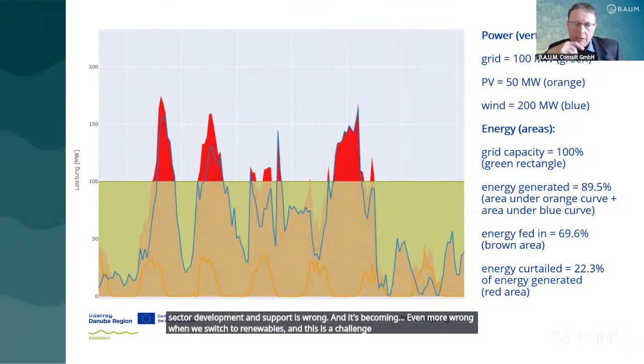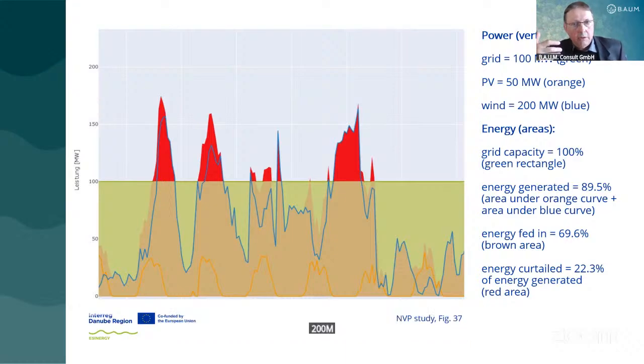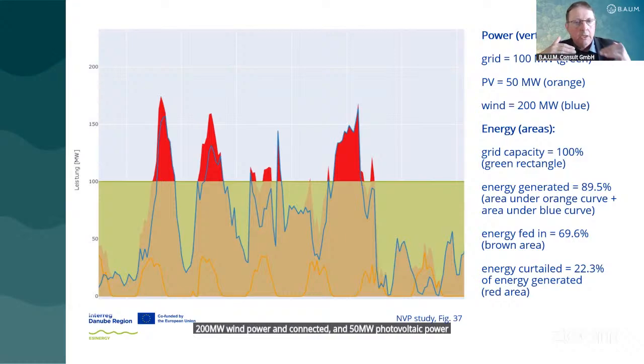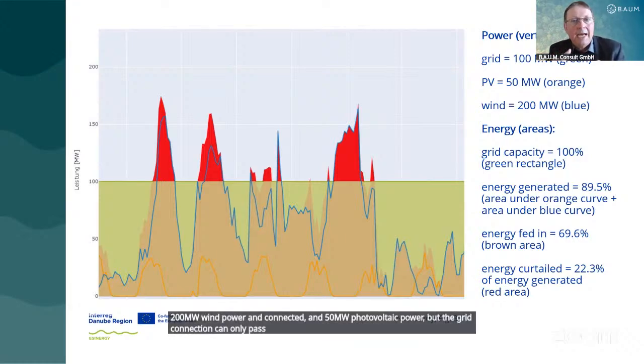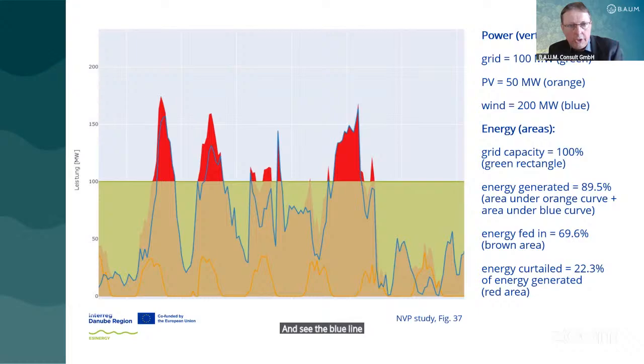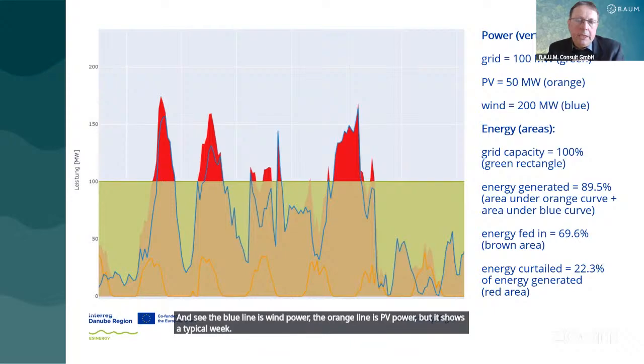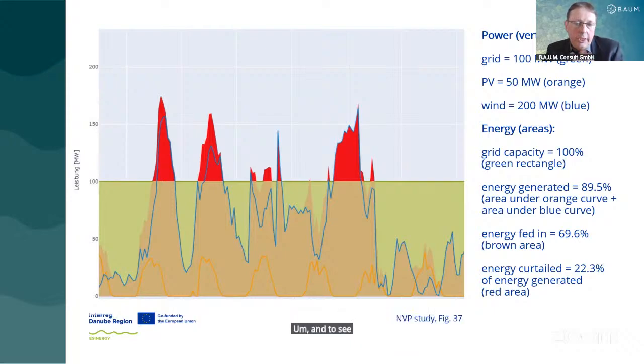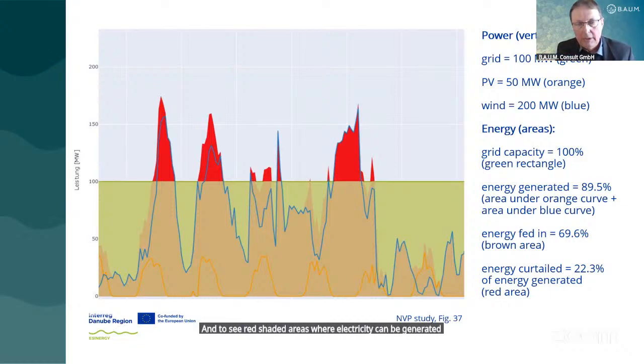This slide shows a situation at the grid connection point where we have 200 megawatts of wind power connected and 50 megawatts of photovoltaic power, but the grid connection can only let pass 100 megawatts. The blue line is wind power, the orange line is PV power. It shows a typical week, and the red shaded areas show where electricity can be generated but cannot be injected into the grid.